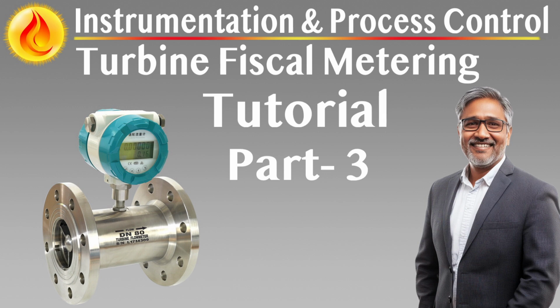Installation must ensure representative measurement by positioning the sensor in a well-mixed section of the stream, typically downstream of flow conditioning and upstream of sampling. The measurement loop must allow for isolation, flushing, and sensor replacement without process interruption. Materials must be fully compatible with crude oils and any expected contaminants or additives.